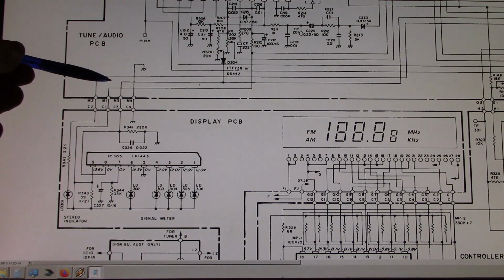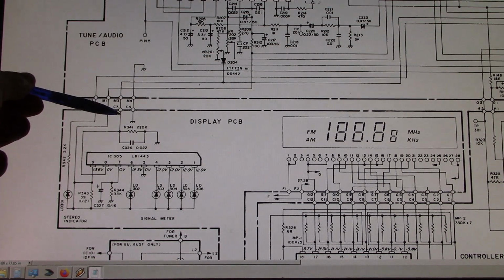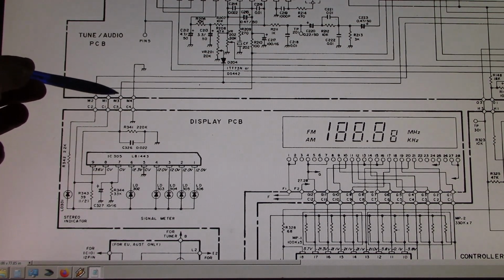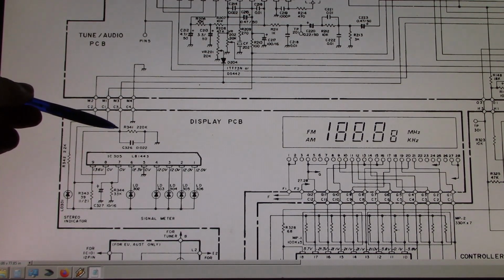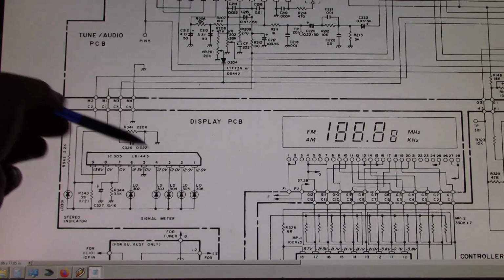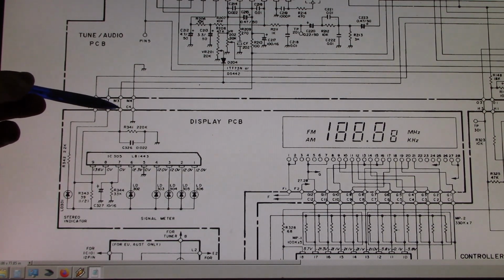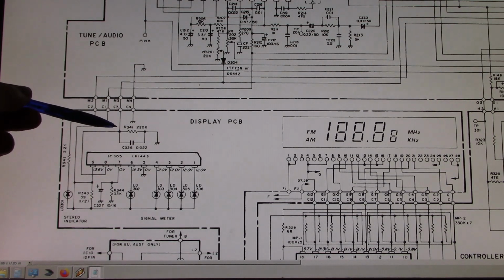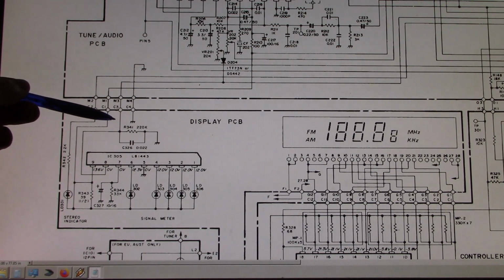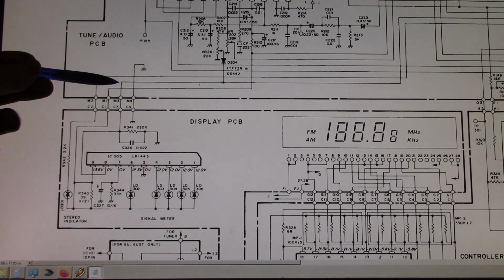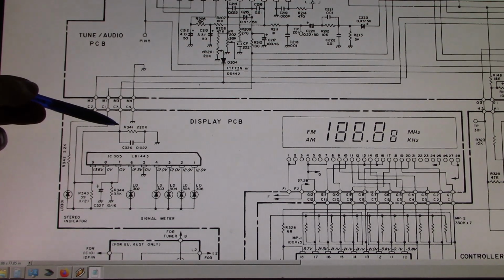Now I'm getting a phantom voltage on this line here, M3C3. This is the signal strength line, so if there's a voltage on here, the meter responds. When I first turn on the receiver, I'm getting about half a volt on this line. It's a phantom voltage, and I'll explain why I call it that in a minute. Then as time goes on, it slowly drops down to 300 millivolts, 150 millivolts or whatever.